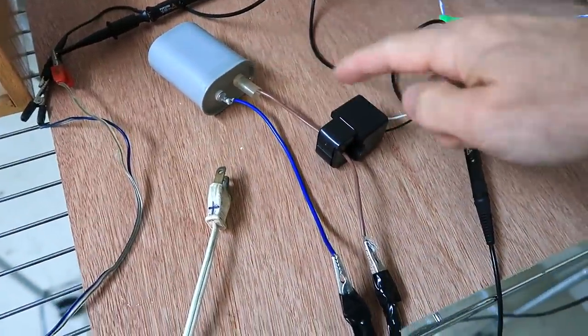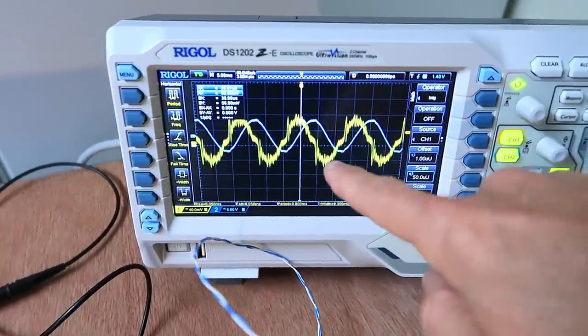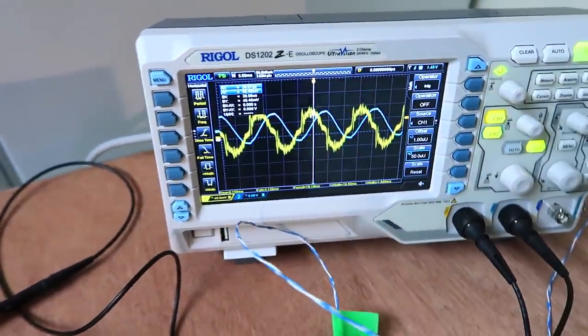So now I hooked up a 16 microfarad capacitor with my current clamp to the scope, hooked up to a power cord. Let's plug that in, and we're getting pretty much the same waveform we got before, maybe just a little bigger. So that mini split, even while it's off, leaves something like a 16 microfarad capacitor hooked up to the line.